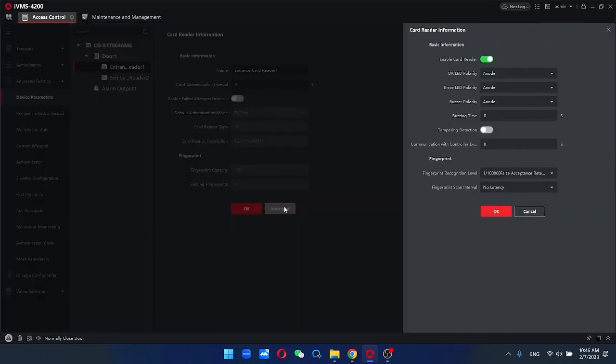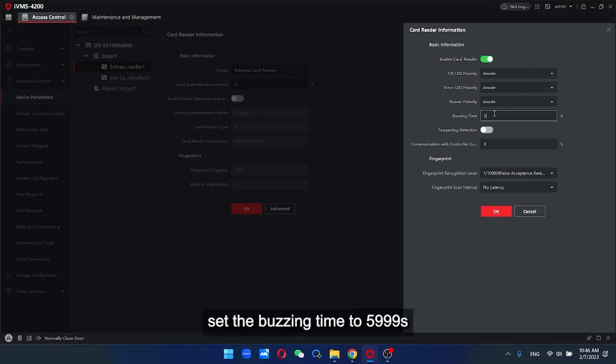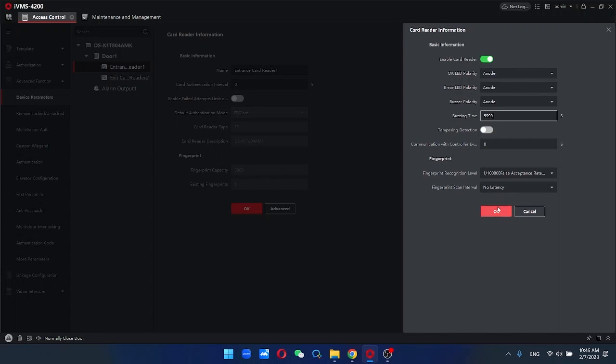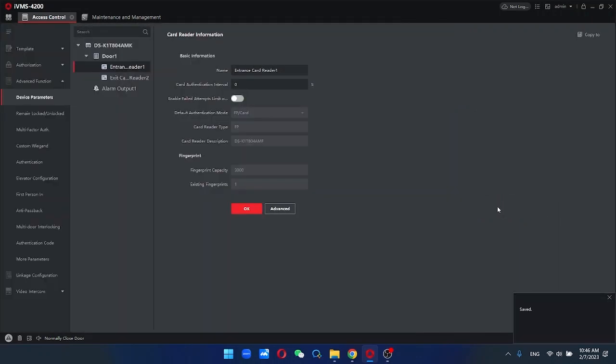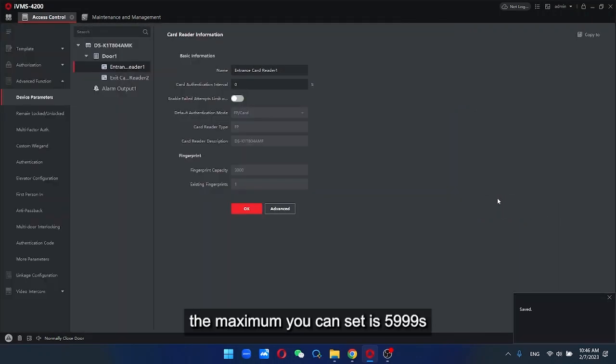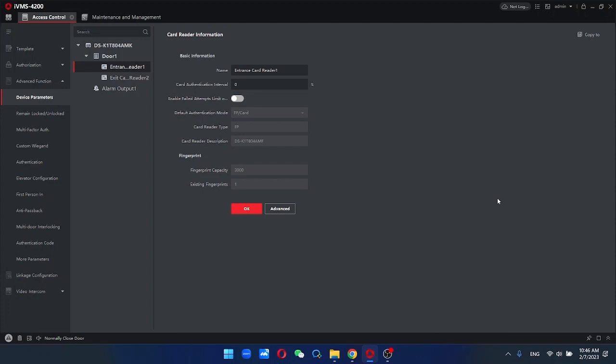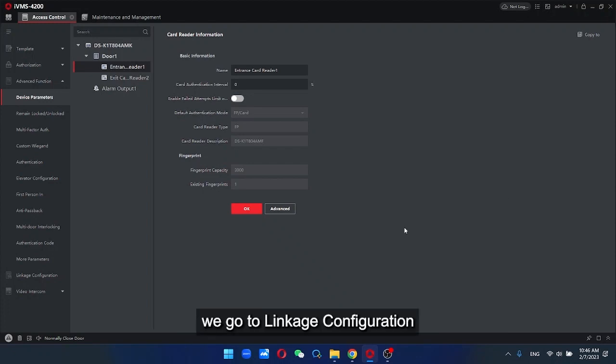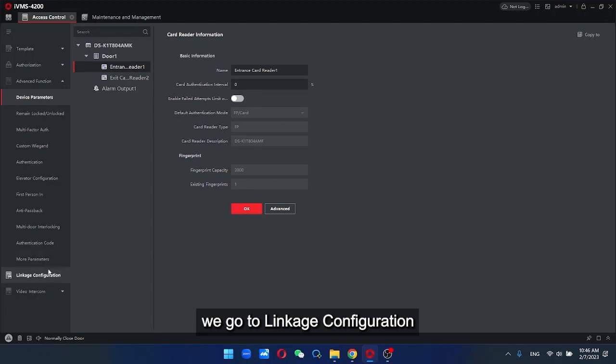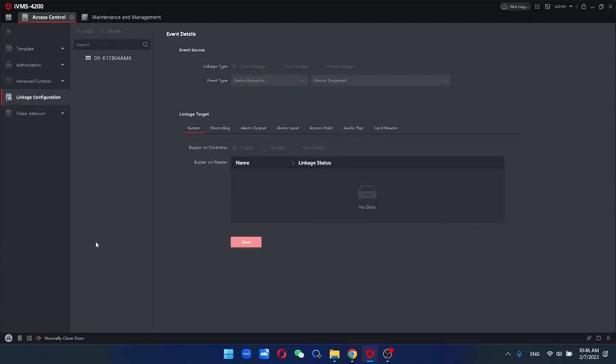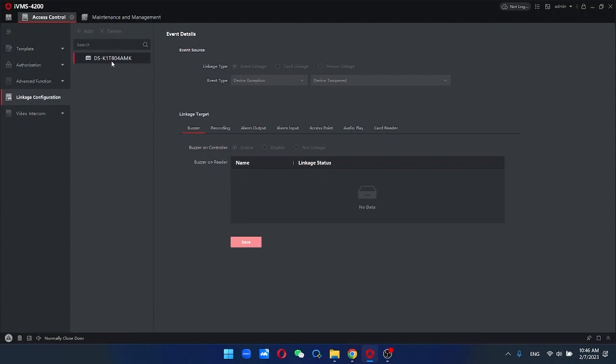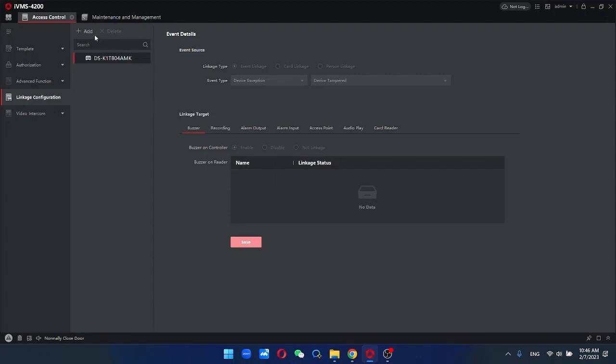Set the buzzing time to 5999 seconds. The maximum you can set is 5999 seconds. Next, we go to linkage configuration. We need to set two linkages under the selected door.